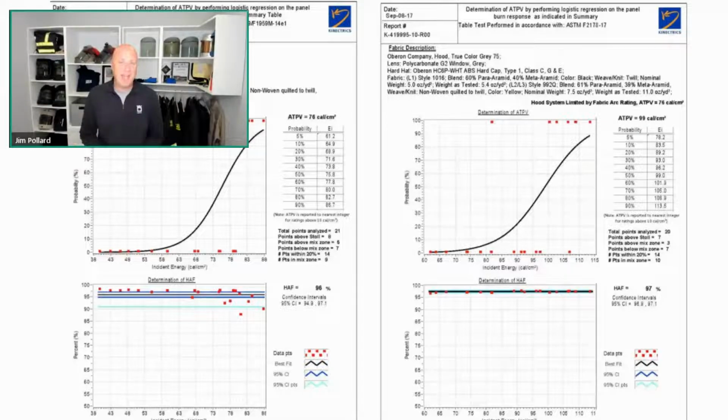In fact, the ASTM standards that apply to the clothing, so the fabric testing or hood testing, face shields, all of those different ASTM standards, there's a requirement for the manufacturer to make that available to you as the end user. So grab that test report, keep it on file, and in terms of the conformity level, these test reports must be within 5 years.